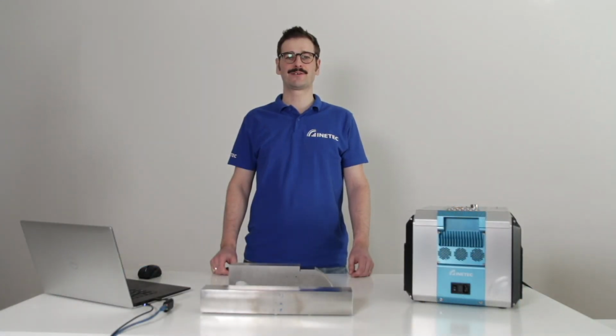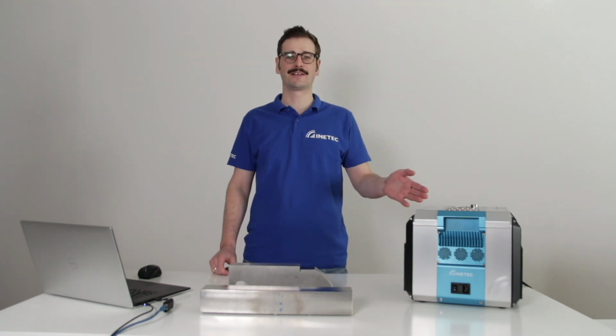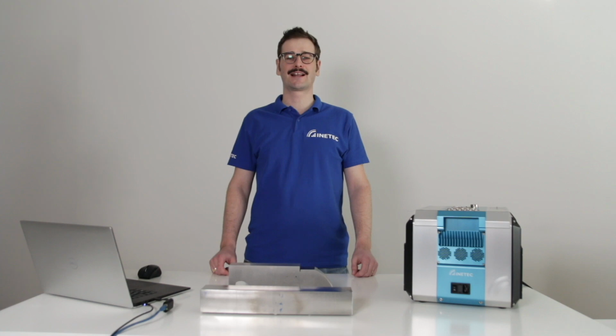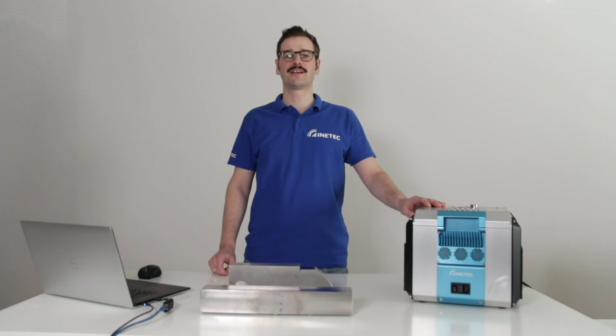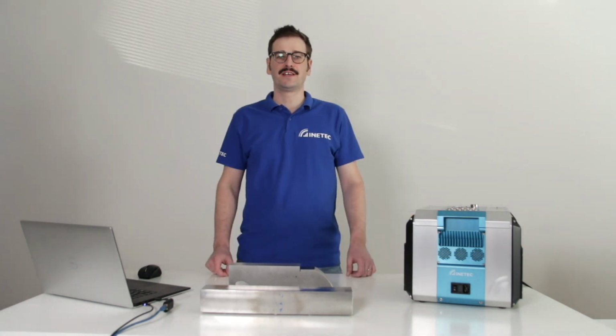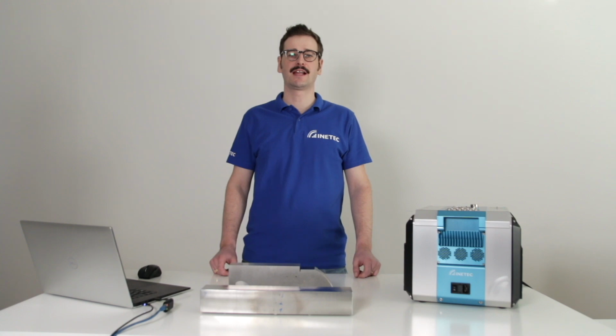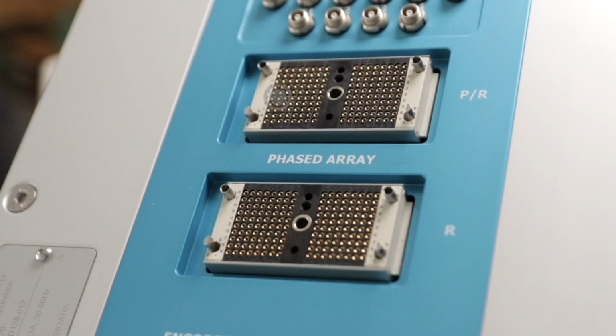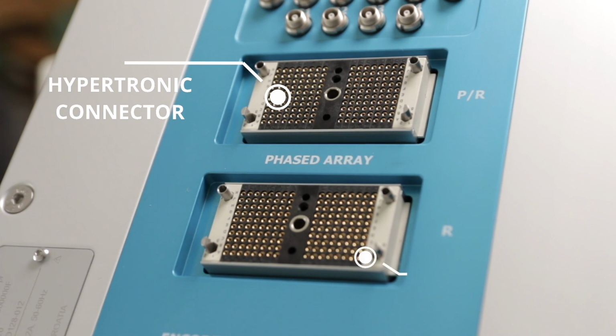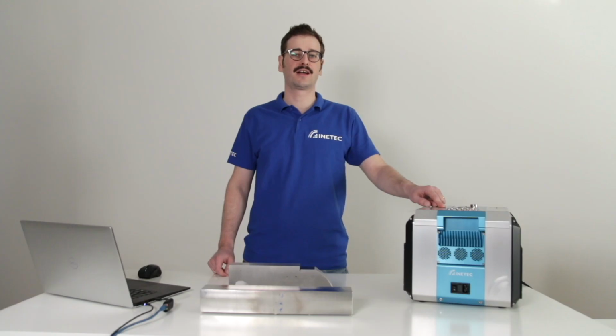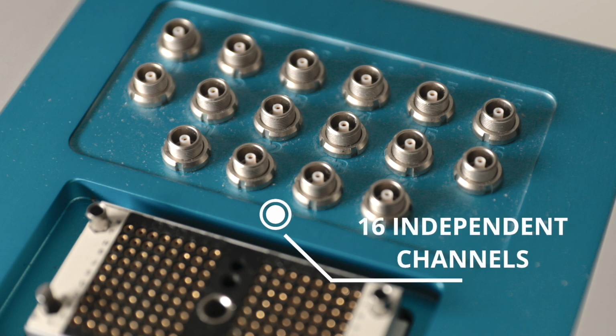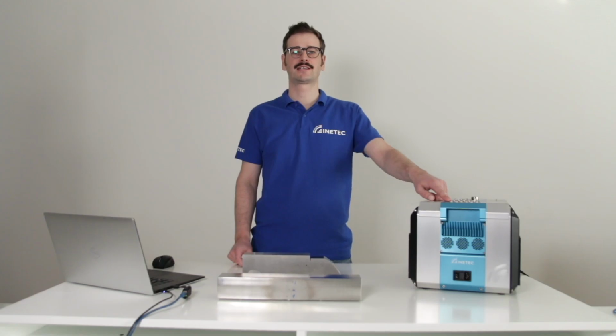We are proud to introduce you to Dolphin 128 by 128 PR, Inetec's best-in-class phased array ultrasonic instrument. All types of probe can be connected to Dolphin, from phased array to conventional, including TOFD. Phased array probes with up to 128 elements can be connected to Dolphin via the hypertronic connector. The second hypertronic connector can be used to connect TRL phased array probes with 128 receivers that are independent from the pulsers. 16 fully independent channels can be used to connect mono and dual element ultrasonic probes.